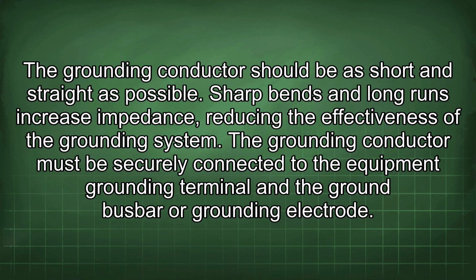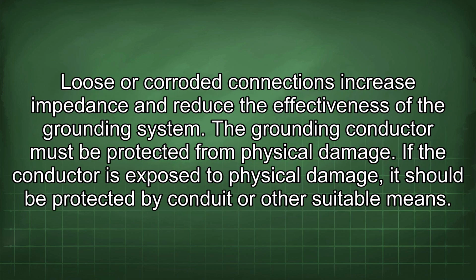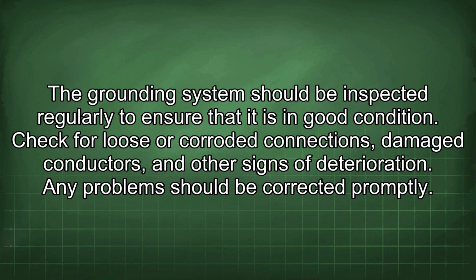The grounding conductor must be securely connected to the equipment grounding terminal and the ground busbar or grounding electrode. Loose or corroded connections increase impedance and reduce the effectiveness of the grounding system. The grounding conductor must be protected from physical damage. If the conductor is exposed to physical damage, it should be protected by conduit or other suitable means. The grounding system should be inspected regularly to ensure that it is in good condition. Check for loose or corroded connections, damaged conductors, and other signs of deterioration. Any problems should be corrected promptly.